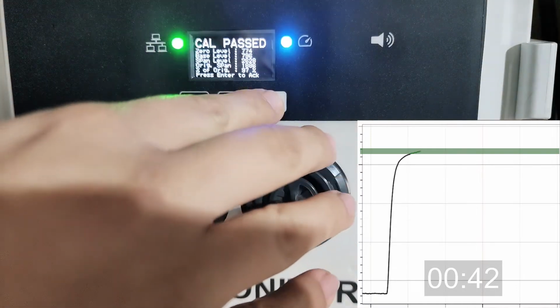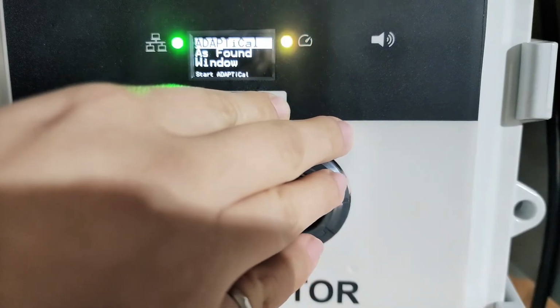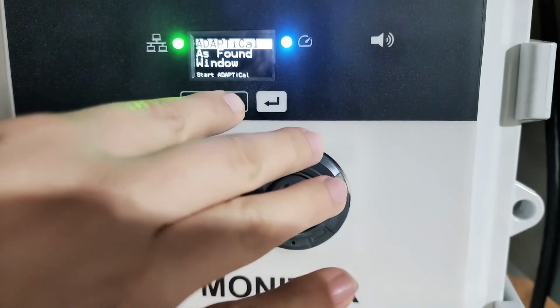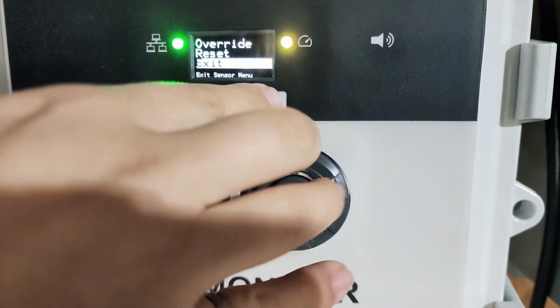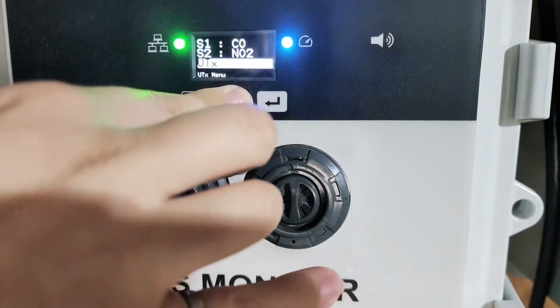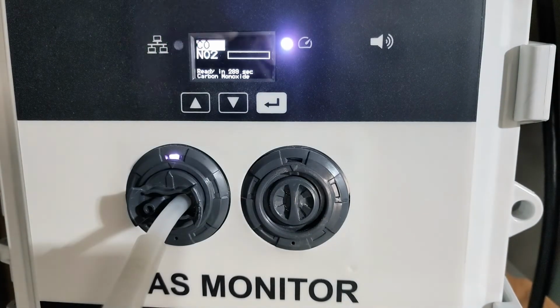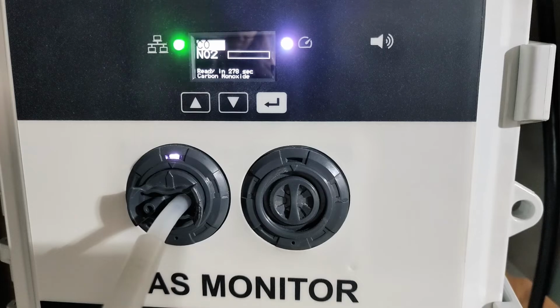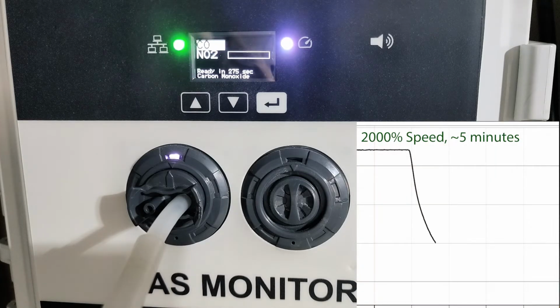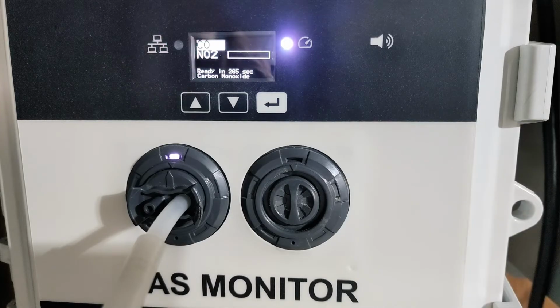To exit, you can hit enter, and then it will either time out, or you can scroll down to the bottom to exit. Again, scroll down to the bottom and exit again. Here you can see that the LEDs are white on the display. The white LED indicates that the unit has entered a 5-minute warm-up mode, which allows time for the sensor output to recover from gassing and return to its original baseline. The unit functions immediately after calibration, however, the best results are ensured after a 5-minute warm-up.